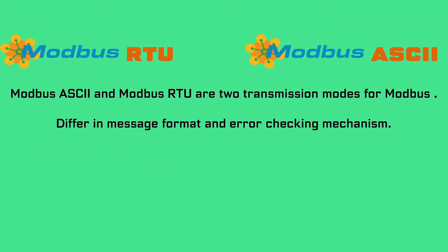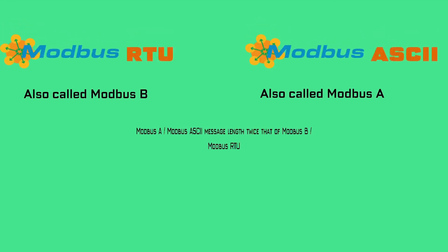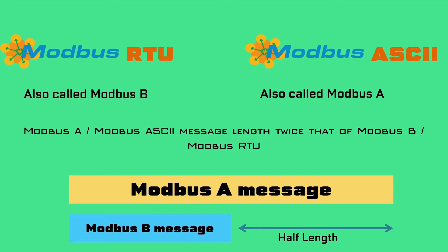ASCII and RTU are the two transmission modes for Modbus and both differ in message format and error checking mechanism. ASCII mode uses ASCII characters to begin and end messages, whereas RTU uses time gaps of 3.5 character times of silence for framing messages. Modbus ASCII is also called Modbus A and Modbus RTU is called Modbus B. Modbus A has a typical message length that is about twice the length of the equivalent RTU message.